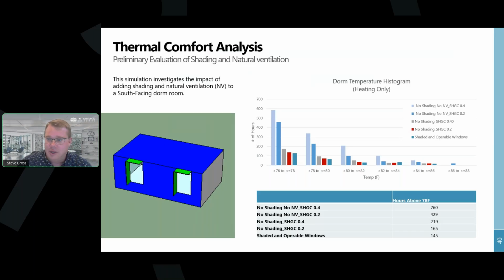The table shows the number of hours per year that temperatures are predicted by the model to be above 78 degrees, chosen as the maximum desired temperature—above that would be difficult to justify from a design standpoint. The first two rows are for reference: modeling the building without natural ventilation, just mechanical ventilation and heating only. We see almost 800 hours above 78 with the higher solar heat gain coefficient, and it's clearly impactful to let less solar energy into the space with a lower solar heat gain coefficient.